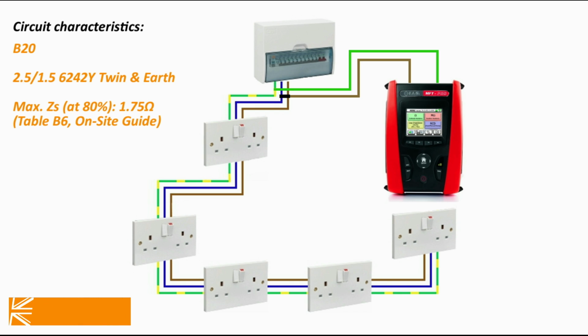If the EMF from the test instrument, usually at 500 volts DC, can short from line conductors to earth and give a failure reading on the tester, then you can expect RCD or AFD tripping through parallel arcing if the upgrade goes ahead. The pain with IR testing for parallel arcs comes with the potential for such a fault to be present on a damaged cable between line and neutral, as that test is often a limitation on an inspection.